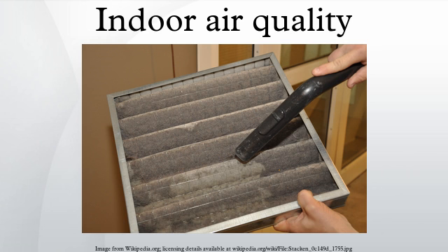In areas where cellulosic materials become moist and fail to dry within 48 hours, mold and mildew can propagate and release allergenic spores into the air. In many cases, if materials have failed to dry out several days after the suspected water event, mold growth is suspected within wall cavities even if it is not immediately visible. Through a mold investigation, which may include destructive inspection, one should be able to determine the presence or absence of mold. In a situation where there is visible mold and the indoor air quality may have been compromised, mold remediation may be needed.